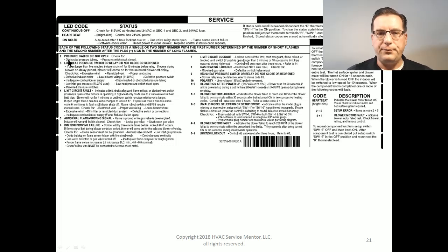Fault codes. Just real quick, I want to reiterate that when you experience a fault code, sometimes there are helpful suggestions to tell you what to check for. Check this out for low heat pressure switch or relay did not close or reopen. There's a bunch of things it could be. And one of them, only one, is a defective pressure switch. There could be all kinds of other things going on there.